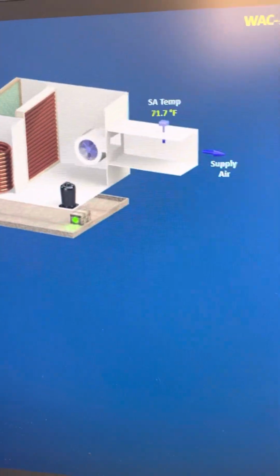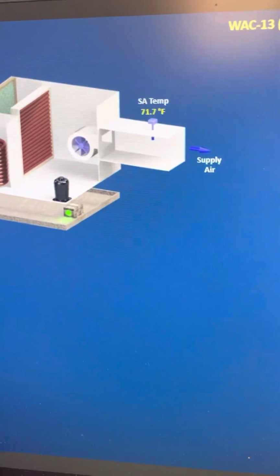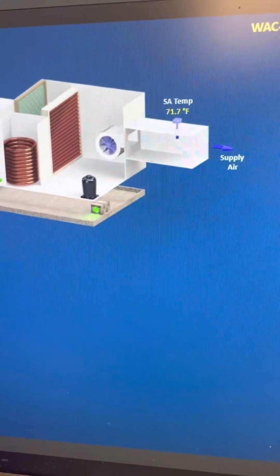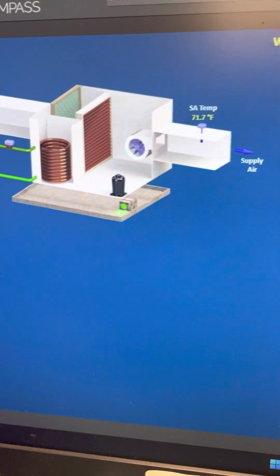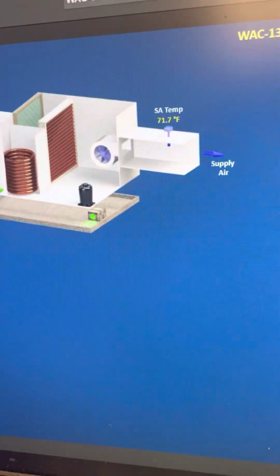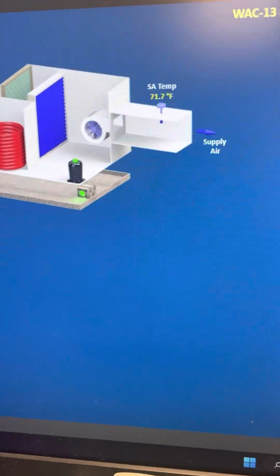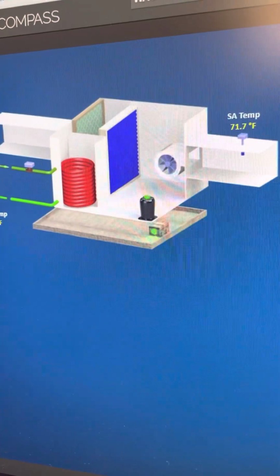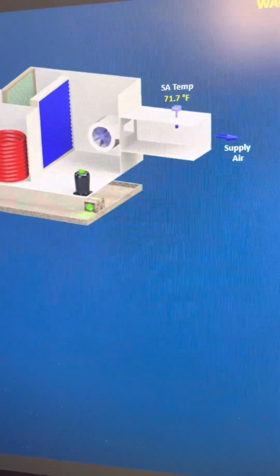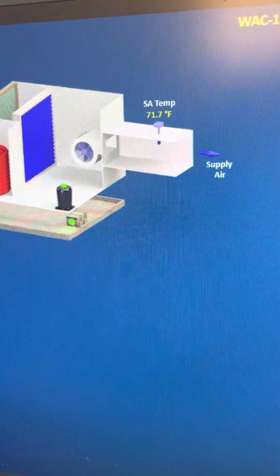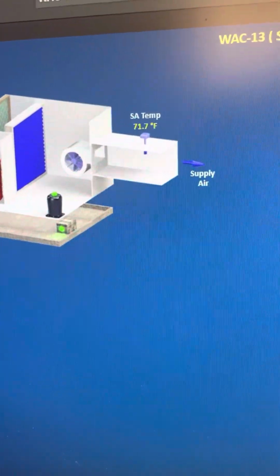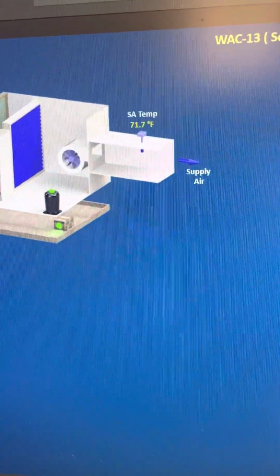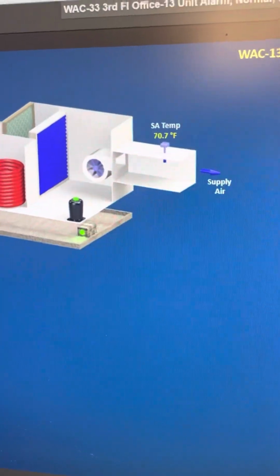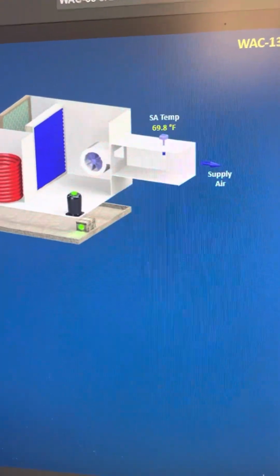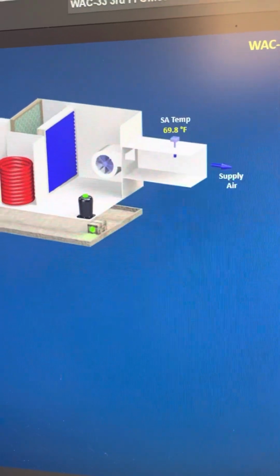All right, 44%. Still, the supply air temperature is at 71.7. So that's telling me that the compressor did not go on yet. A few changes happen when the compressor kicks on. Let's see, I want to try to catch it. Should be any seconds. There we go. Now look, it's showing me the compressor's on, but the supply air temperature is still the same. So in real time, the compressor isn't on. It should be on any other second. You're going to start seeing a drop. There we go. I believe the compressor just kicked on. So it's going to start bringing that down.